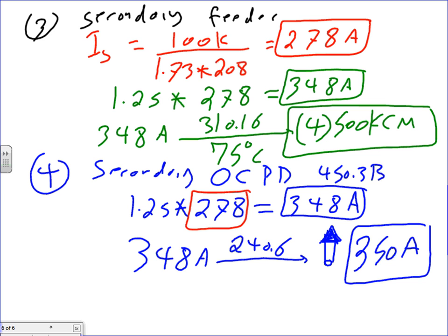Any questions, guys? Before I go on, I want to size two more things: the bonding jumper for the separately derived system and the grounding electrode conductor. And surprise, guys, they are done exactly like what we did for the services. You go to 250.66 for the grounding electrode conductor. For the bonding jumper, it's called the system bonding jumper for a separately derived system, and you also go to 250.66. If it's higher than 1100 kcmil, you take 12.5% of the feeder feeding the transformer. Any questions? Bill, Jim, Camille, Brooks? No?